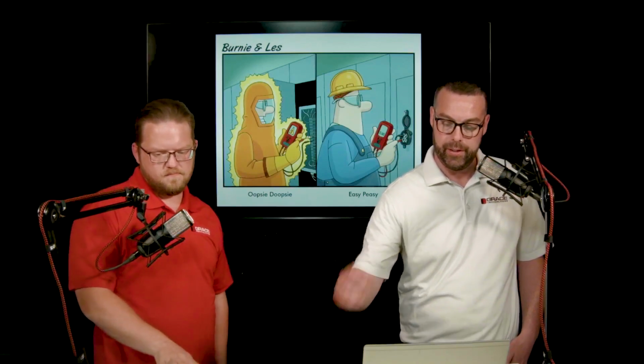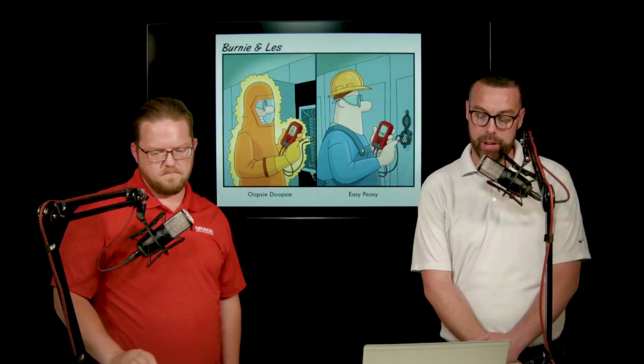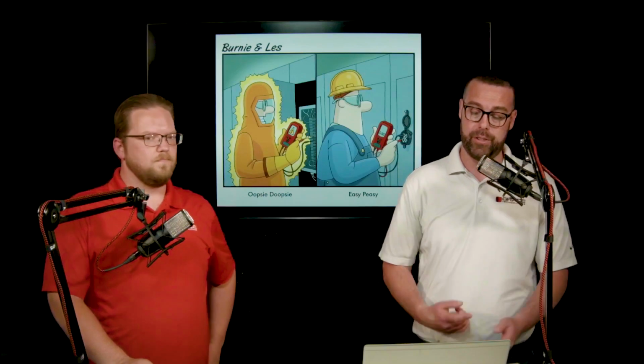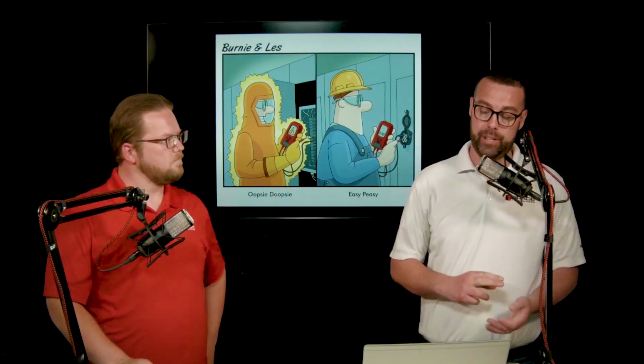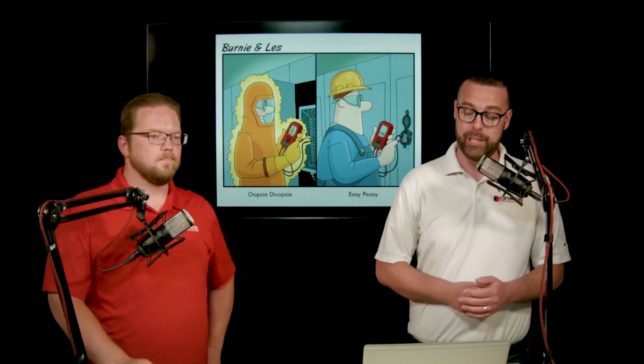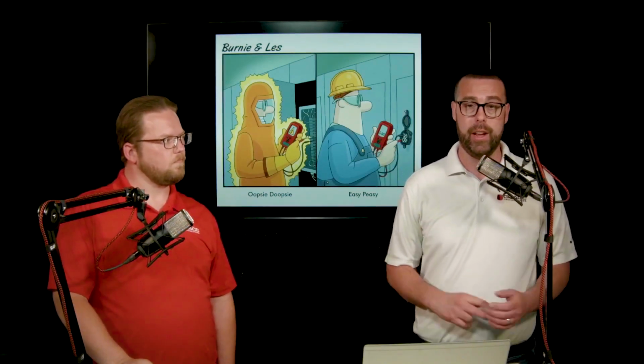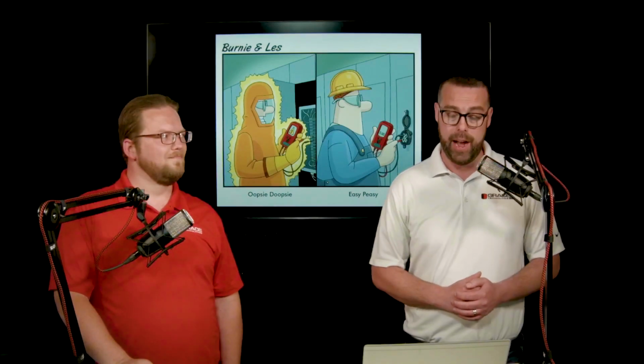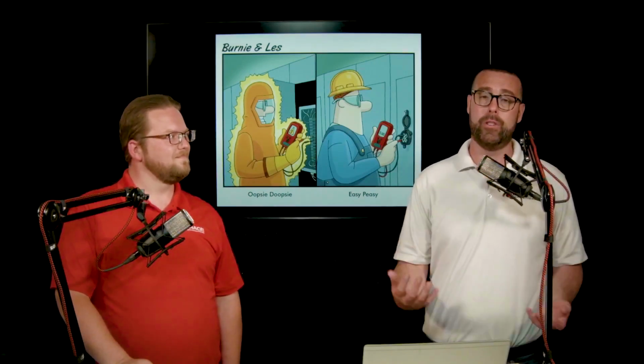Should we use arc flash clothing when servicing 125 volt DC batteries? I believe the answer here is ultimately at your discretion. The decision to use arc flash clothing when servicing 125 volt DC batteries should be based on a thorough risk assessment and compliance with relevant safety standards and regulations. Make sure that when interacting with that level of voltage, you're properly suited up in PPE that is required or rated for that specific application and environment. The last thing we want is for you to expose yourself to that inherent risk and create an arc incident. So doing that initial risk assessment and identifying the properly rated PPE would be our recommendation.